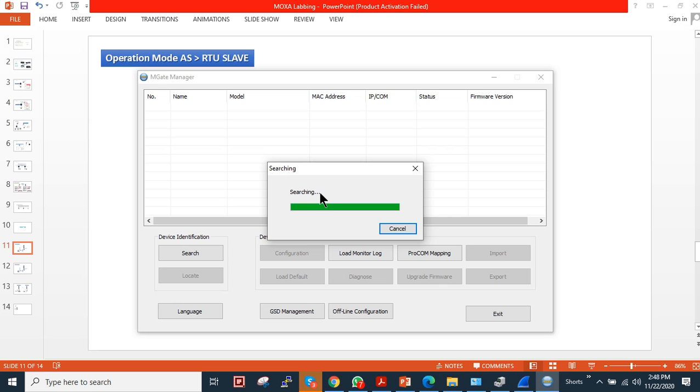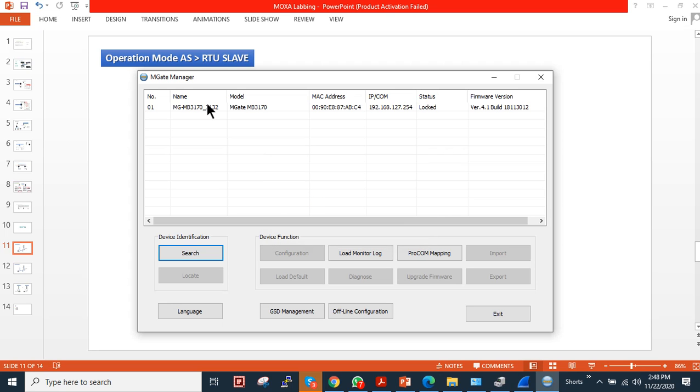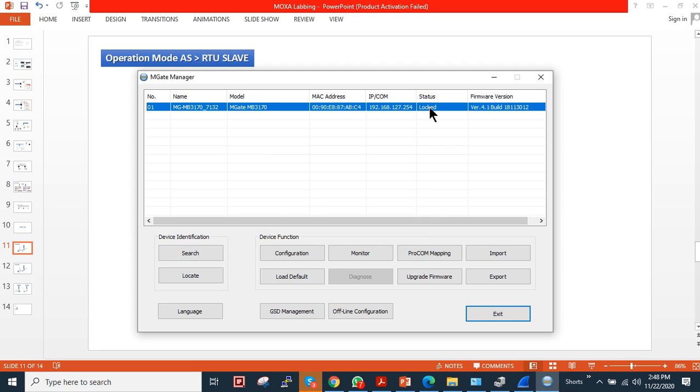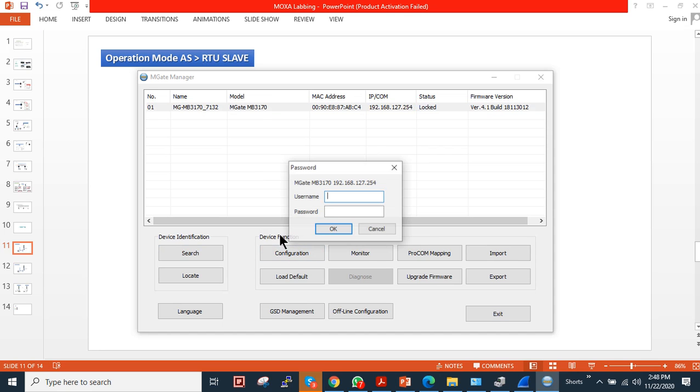It will just take a little bit of time. As you can see, the device is discovered and it is showing locked. Once you click, you have to choose the device and click on configuration. It will ask you for the username and password. Username is admin and password is moxa. Click okay.